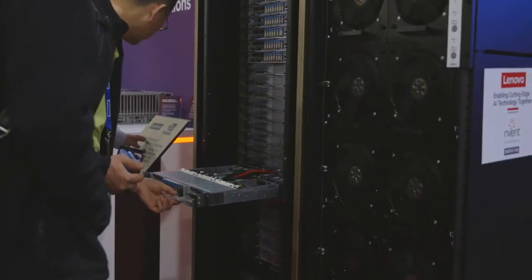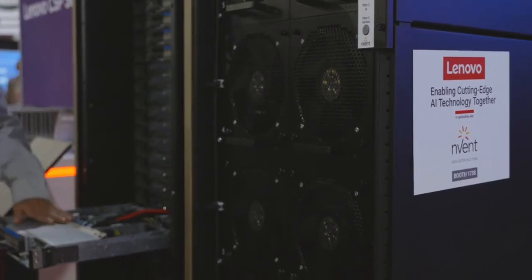And tell us what's the new big thing from Lenovo this year? So this year, we just announced our next generation direct water cooled system, starting with the next gen Intel Granite Rapids AP system, which we're showcasing also on the floor. This one was designed from the beginning for 100% water cooling. One of the big things here is that we don't need PDUs anymore in the racks. We have a new power conversion station, which is basically a power supply, but we got rid of all the transformers and everything. So we directly use 32 amp or 63 amp current from the electricity grid. That makes it a lot easier for cabling and for the supply of power to those systems.